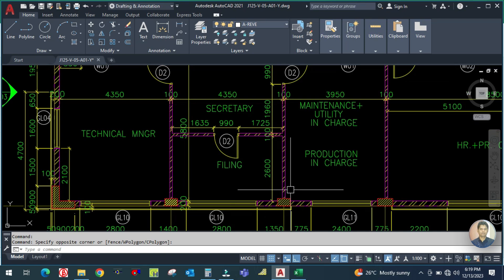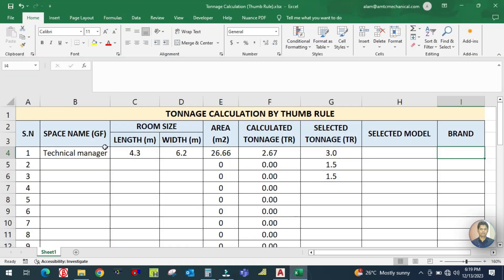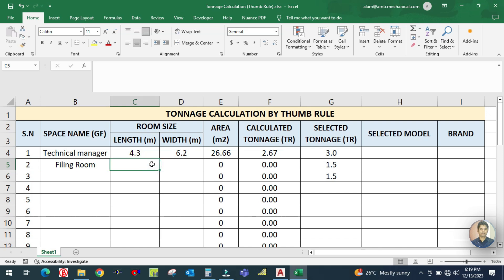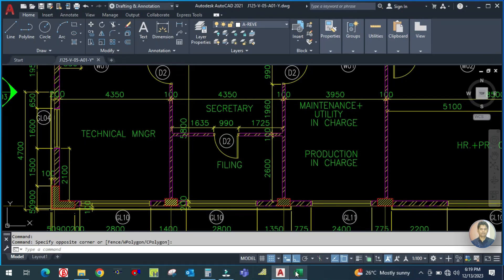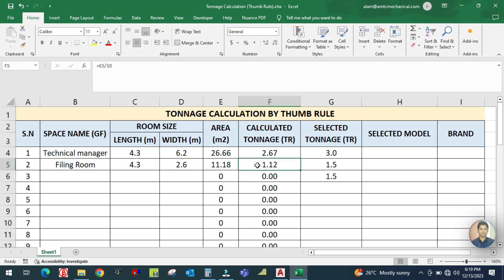For the second space, the Filing Room, the dimensions from the drawing are 4.3 meters length and 2.6 meters width. Simply enter 'Filing Room' as the space name, then enter the length as 4.3 and the width as 2.6. The calculated tonnage comes to 1.2, and since 1.2 is not available, you go for the next higher capacity, which is 1.5 tons.